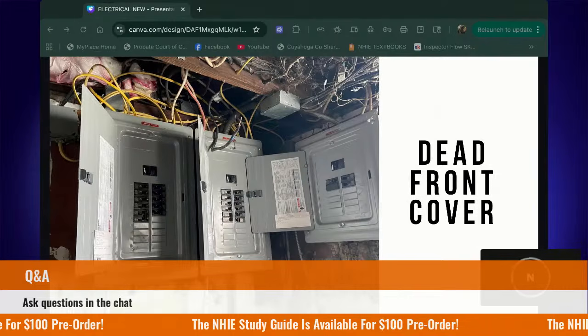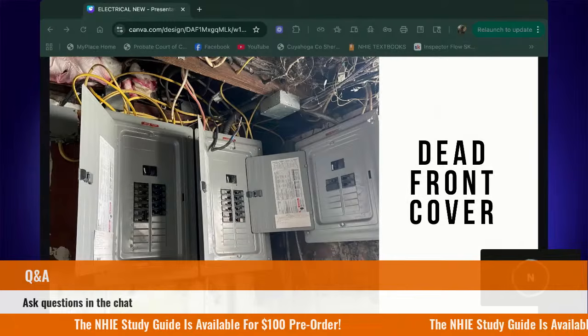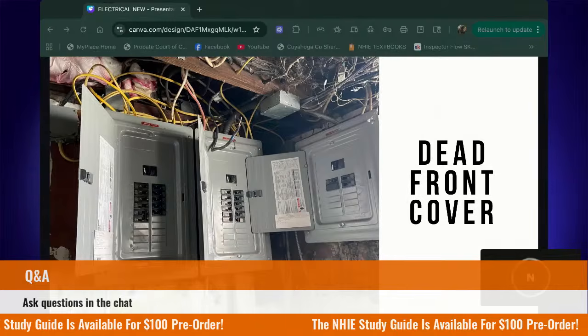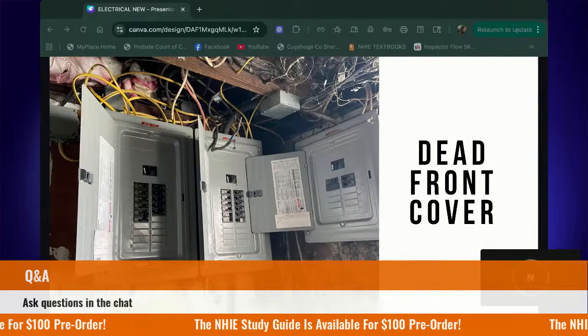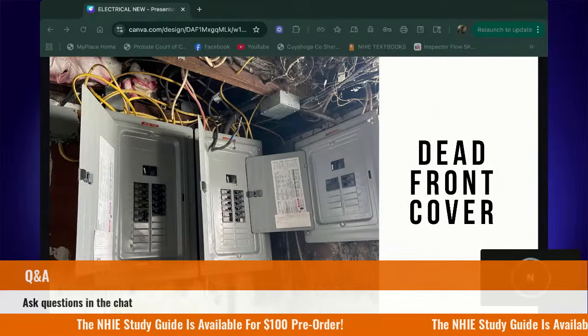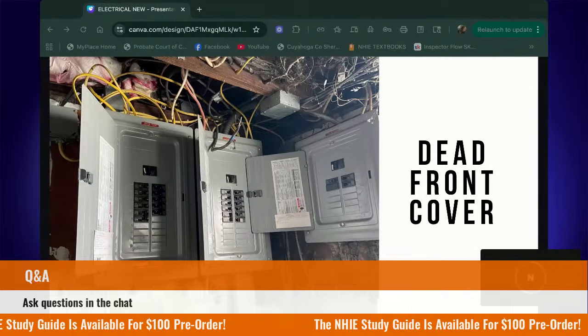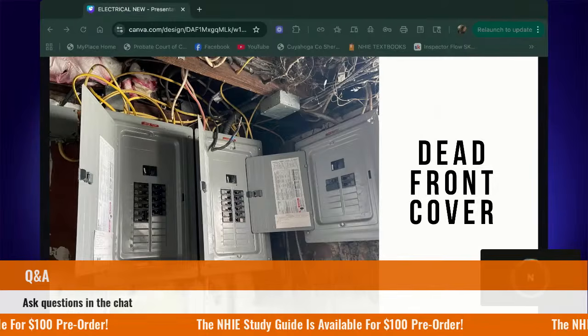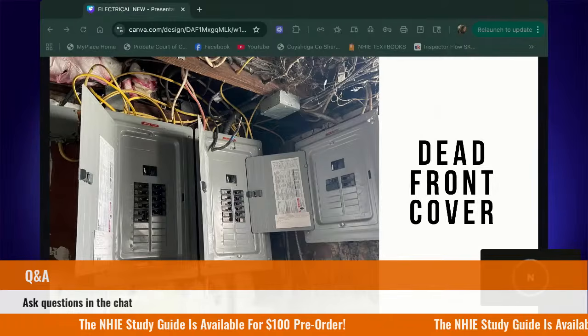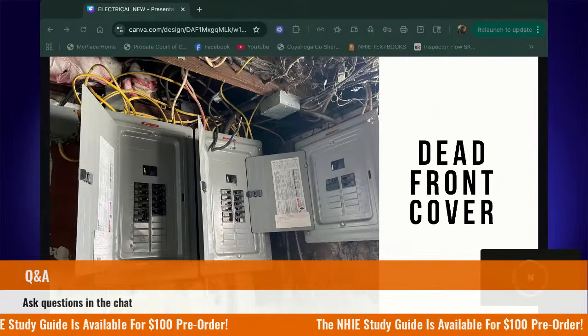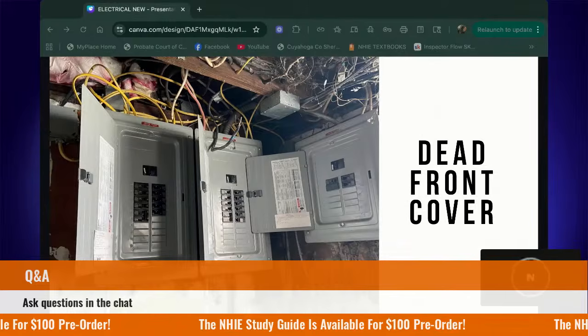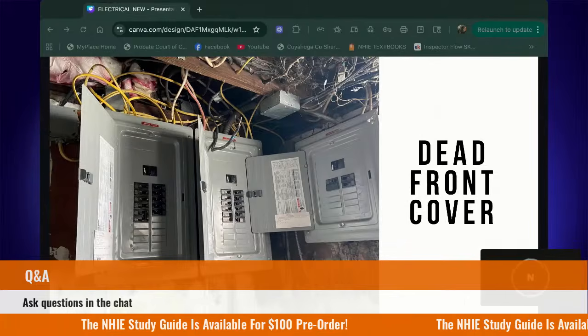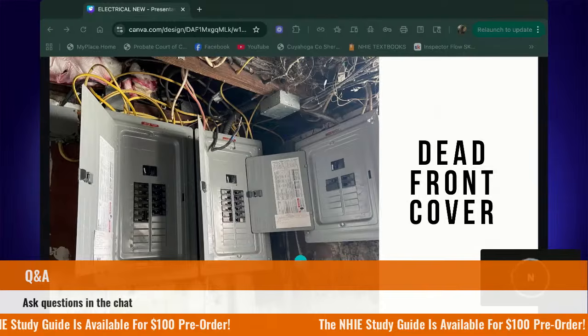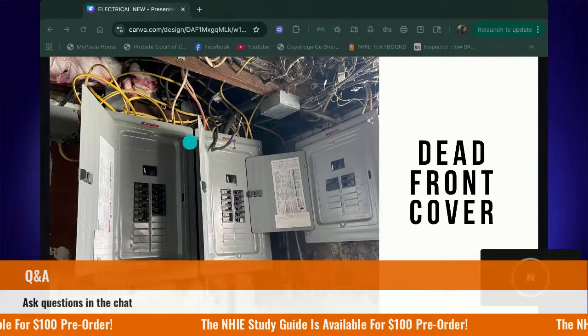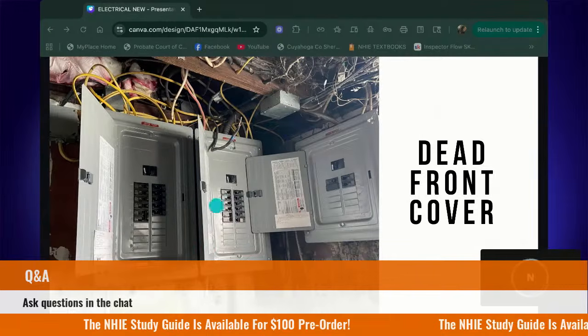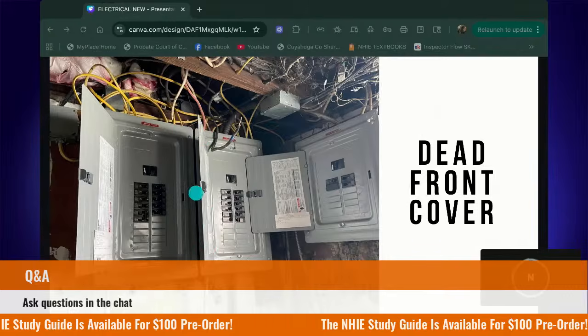Okay. You have to always assume that the panel is energized, meaning that it has power. It's important that you always, I'm guilty, I don't always wear eye protection, but you should always wear eye protection, because that's why they're called accidents, because you didn't mean for them to happen. You didn't know that they would happen, and you want to be prepared. So eye protection, insulated gloves, and you have to be careful when you are removing the screws, because again, you're going to be removing them one at a time.